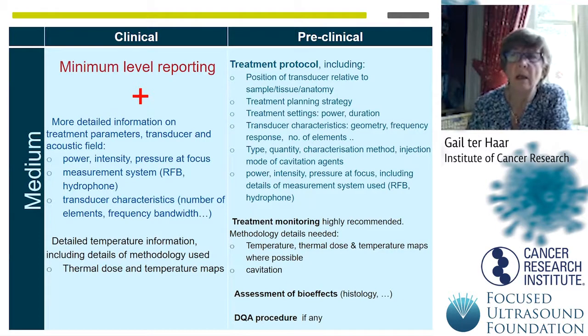Is it using a radiation force balance or a hydrophone, or preferably a radiation force balance with a hydrophone? And what are the transducer characteristics? And then we need detailed temperature information, including details of the methods used, so thermal dose and temperature maps.